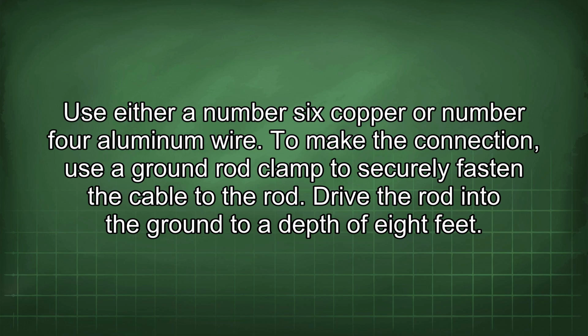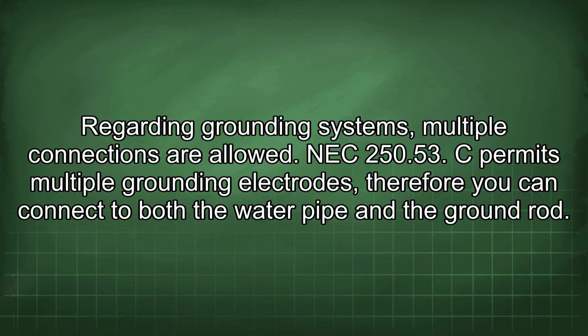To make the connection, use a ground rod clamp to securely fasten the cable to the rod. Drive the rod into the ground to a depth of 8 feet. Regarding grounding systems, multiple connections are allowed. NEC 250.53 C permits multiple grounding electrodes, therefore you can connect to both the water pipe and the ground rod.